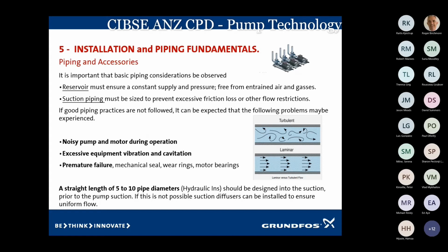If we have restrictions in the pipework and bends and valves and bits and pieces, then the pump's going to be noisy during operation. It's going to vibrate. It can possibly cavitate. Again, premature failure, mechanical seals and motor bearings.